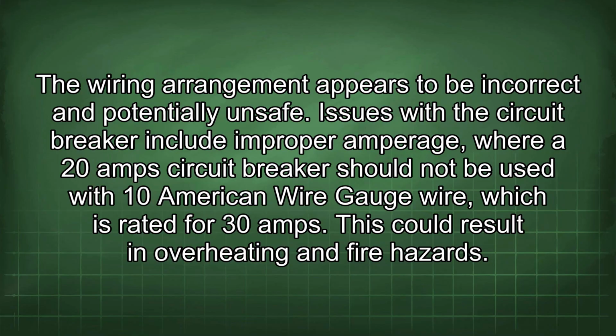The wiring arrangement appears to be incorrect and potentially unsafe. Issues with the circuit breaker include improper amperage, where a 20 amp circuit breaker should not be used with 10 American wire gauge wire, which is rated for 30 amps. This could result in overheating and fire hazards.